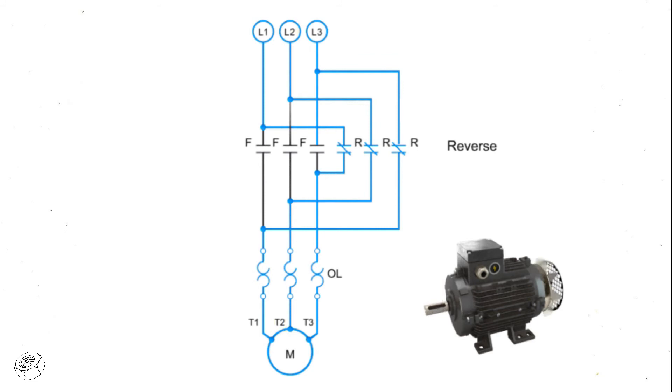This reversal of contacts will cause the motor to run in the opposite direction. Great care must be taken with forward and reverse circuitry, because if the forward and reverse contacts ever engage at the same time, it will cause a destructive and dangerous short circuit.